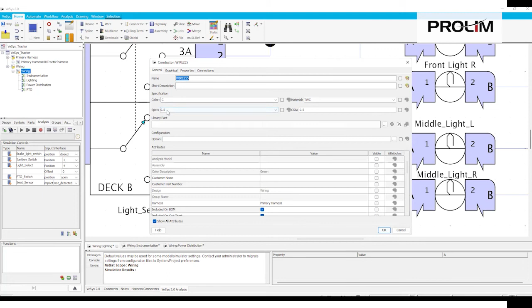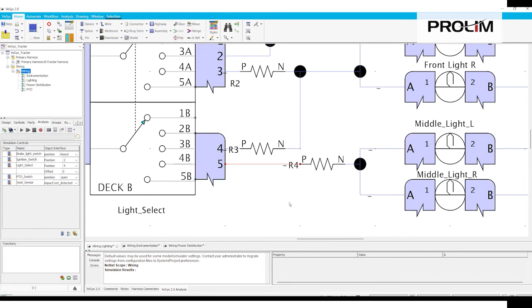So you can see that we are meeting those lighting conditions, but as you can see here, we've got this purple indicator here. A purple indicator does not indicate failure, but if we hover over the line, we can get a little bit more information. So we can see the rated and the max. The rated is 5.09, but you can see that currently it's at 5.4. So it's above and approaching its maximum level. So it's indicating that maybe you want to change the spec for appropriate power usage. So I'll double click that line, go back into the general tab, and we're going to go ahead and just change the spec from a 0.5 to a 1.5. And that should fix our problem.